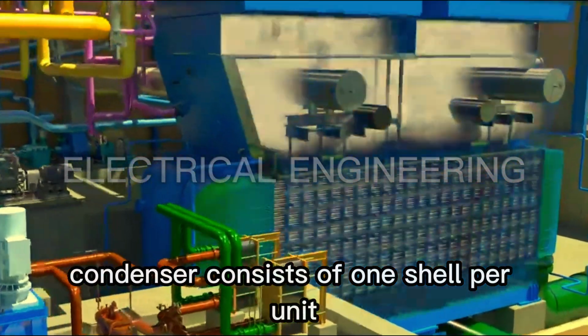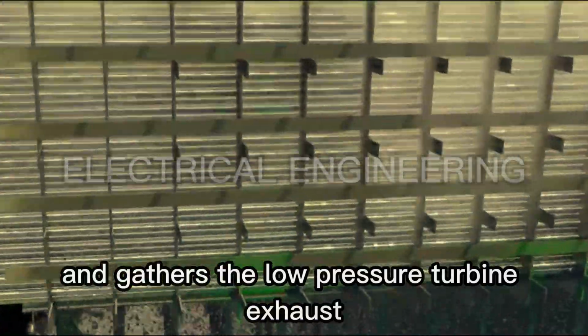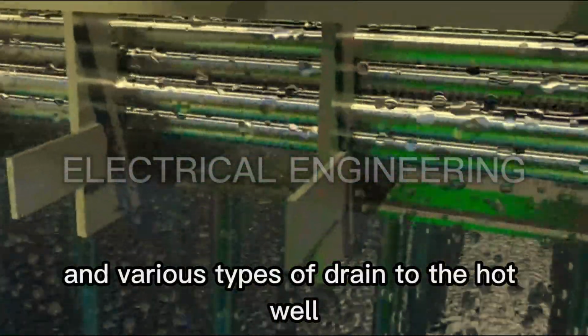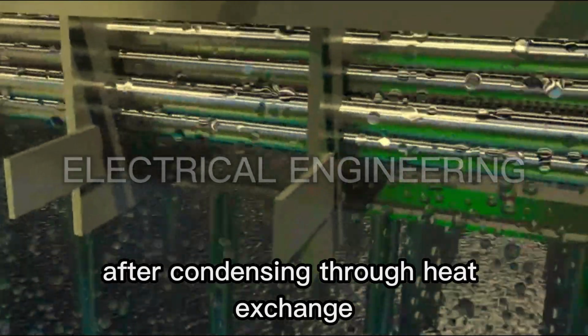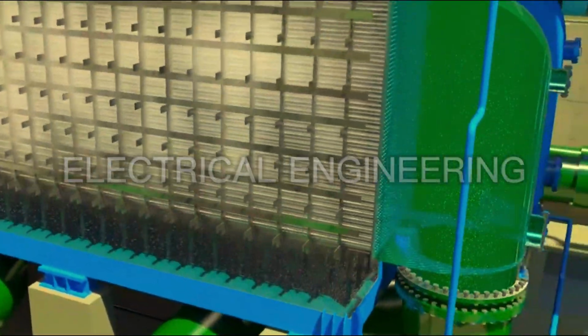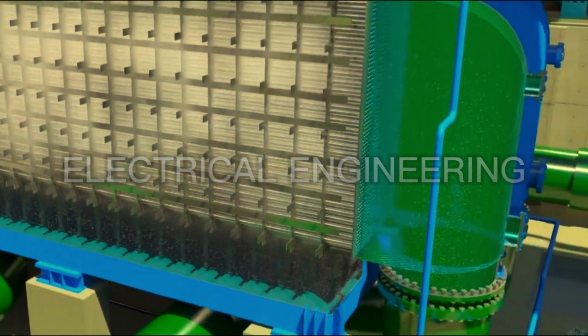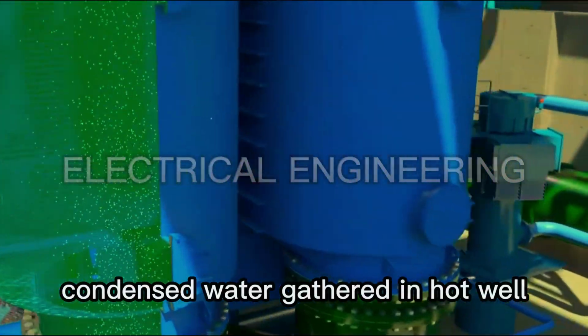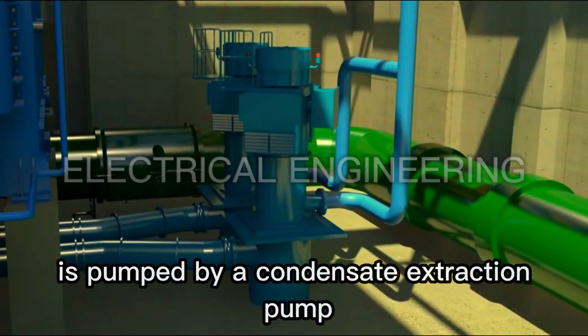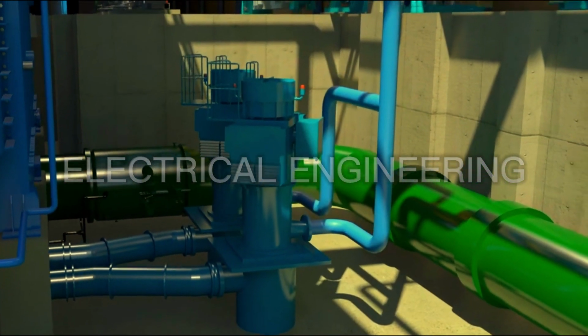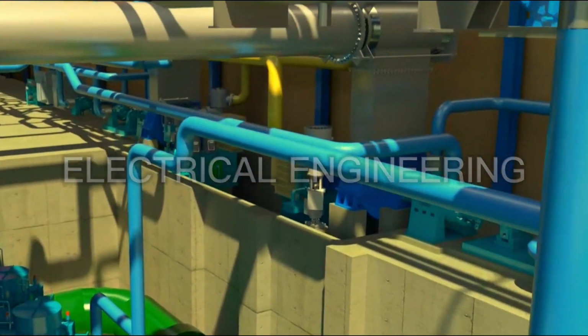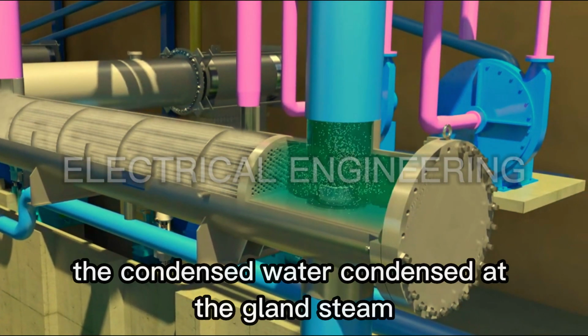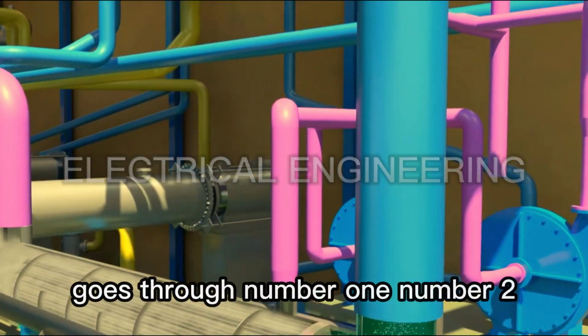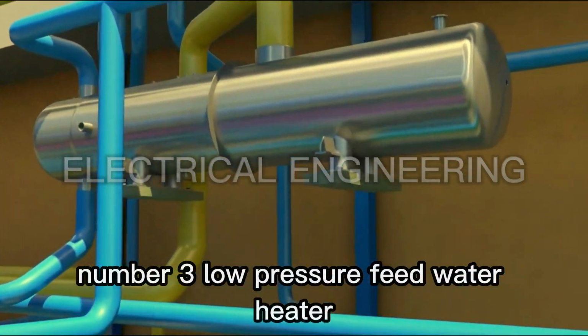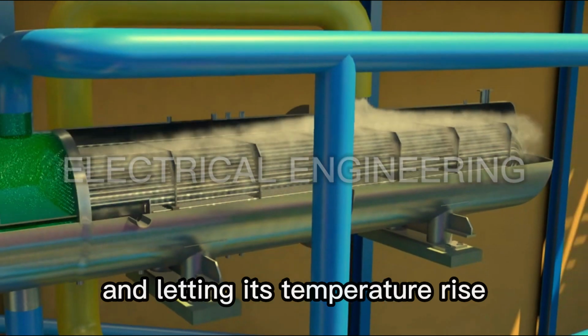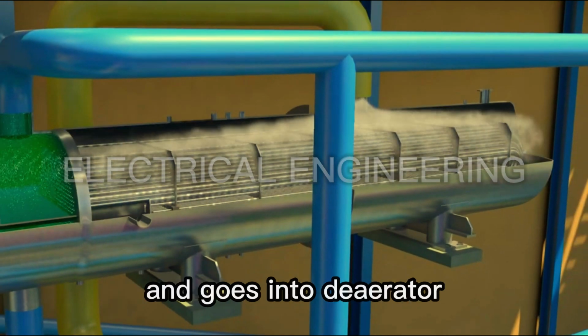Condenser consists of one shell per unit and gathers the low-pressure turbine exhaust and various types of drain to the hot well after condensing through heat exchange by cold seawater. Condensed water gathered in hot well is pumped by condensate extraction pump and is sent to gland steam condenser. The condensed water goes through number 1, number 2, number 3 low-pressure feed water heater, letting its temperature rise, and goes into deaerator.